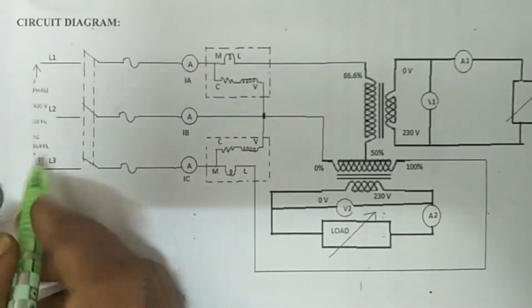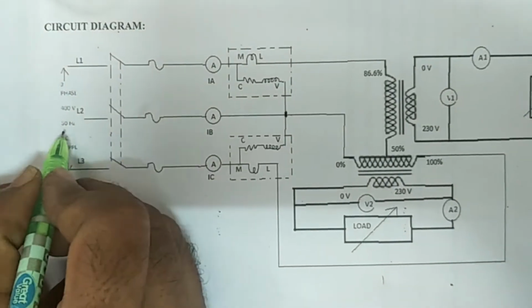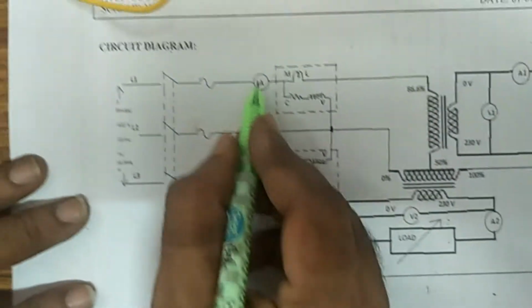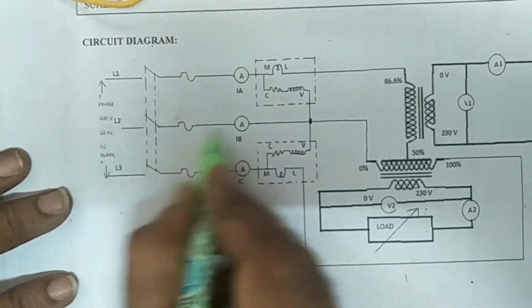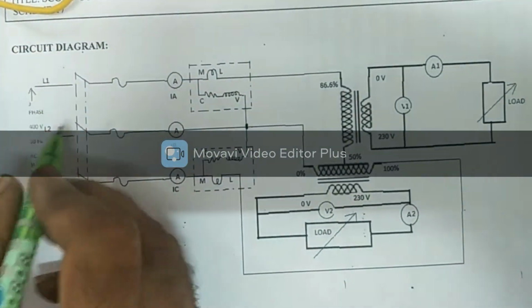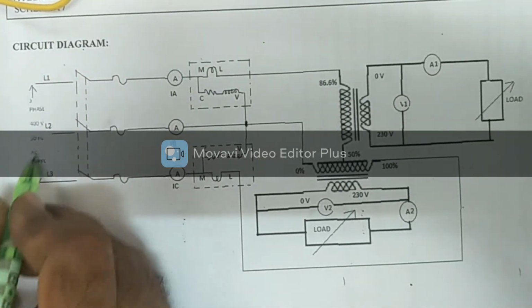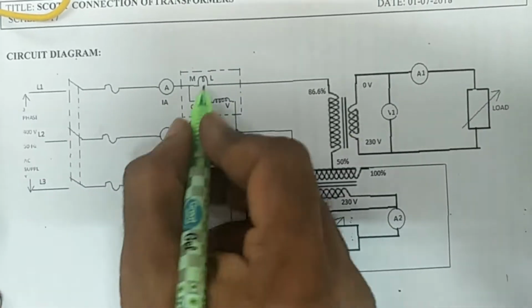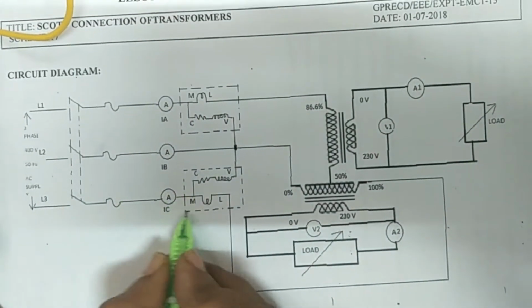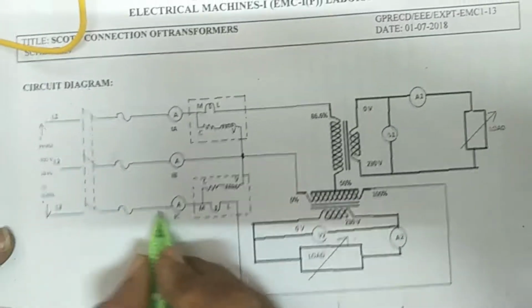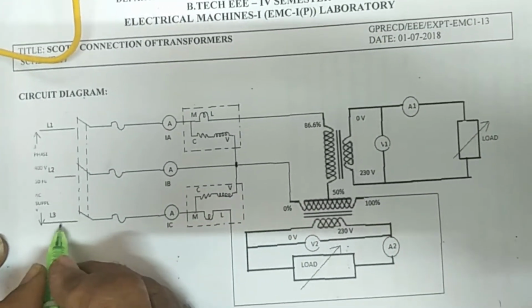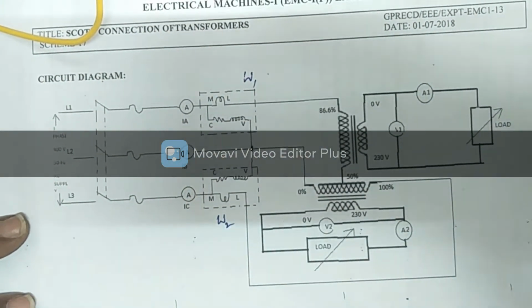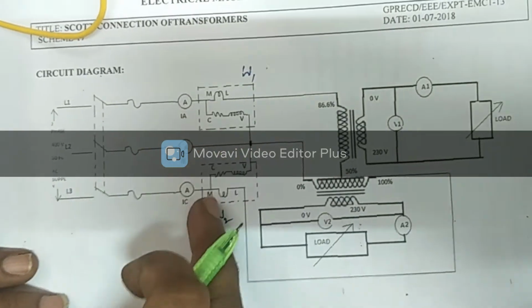There is a three-phase supply. The three-phase input voltage is 400 volts, 50 Hz three-phase AC supply, and you are going to take three currents, that is, three ammeters in the lines. You can imagine these as the three lines L1, L2, L3. In each line you have an ammeter, and a voltmeter is connected between two lines. Here a wattmeter is connected between the lines L3 and L2. Like that you take two wattmeters, W1 and W2. The purpose of these wattmeters is to measure the total input power.